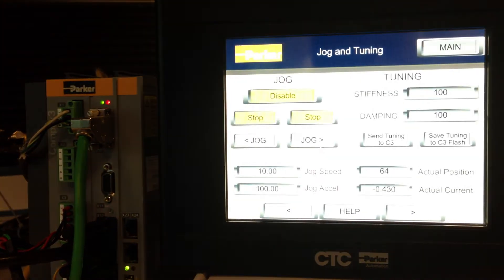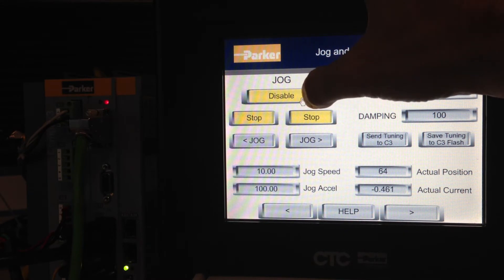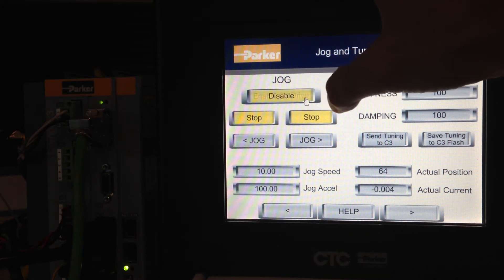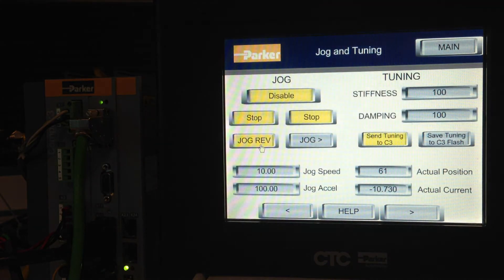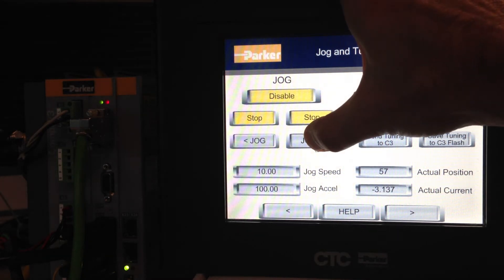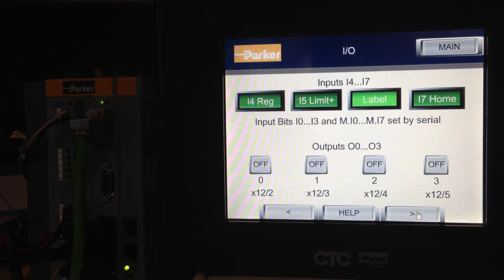On the jog panel, to recover from that, you can toggle the ENABLE input — that re-enables the drive. You get a solid green LED and then you can jog off of it. If you go to the IO panel, you can see I-5, which is the positive end of travel, is lit and activated.